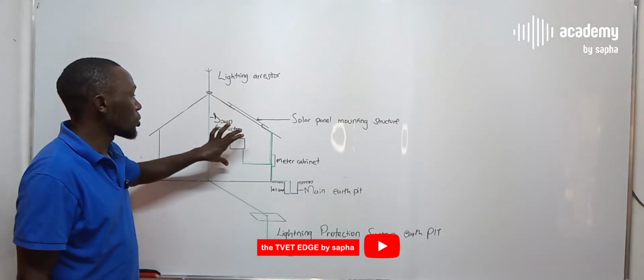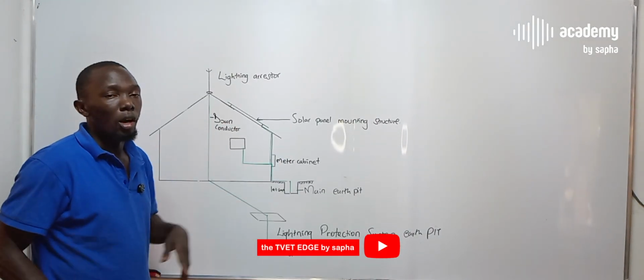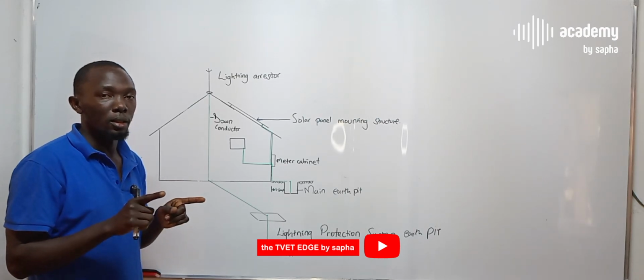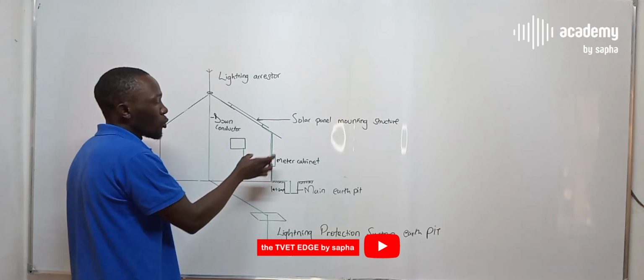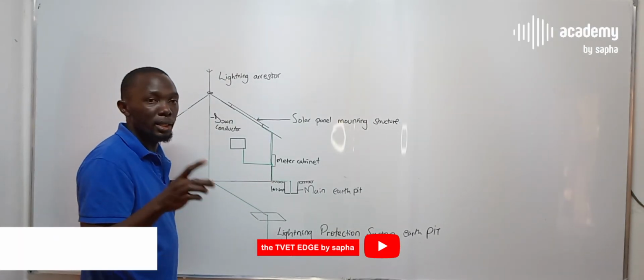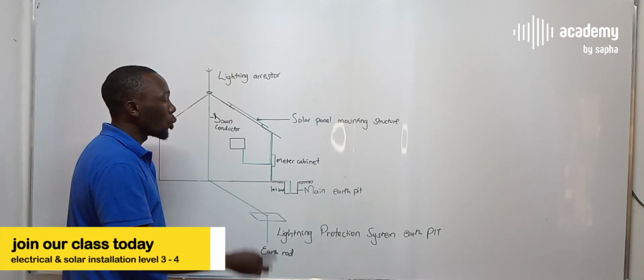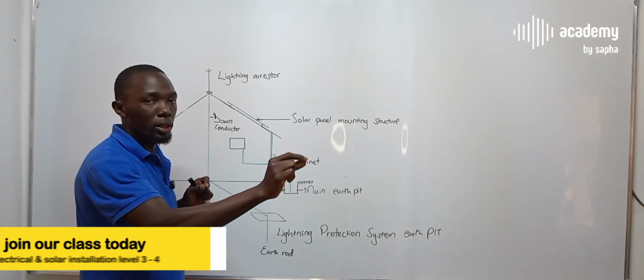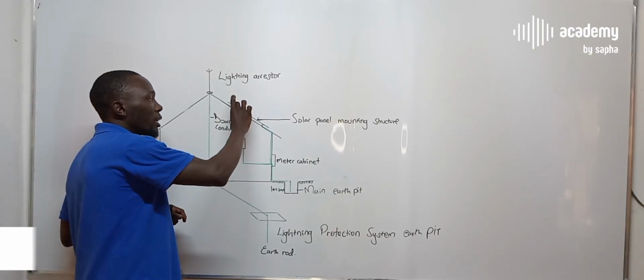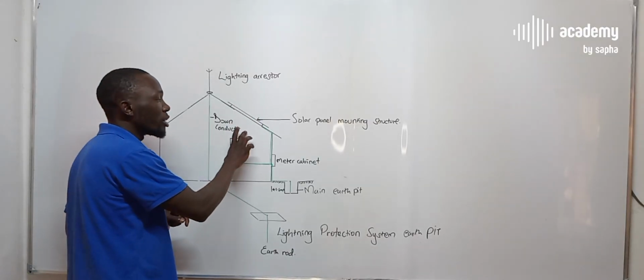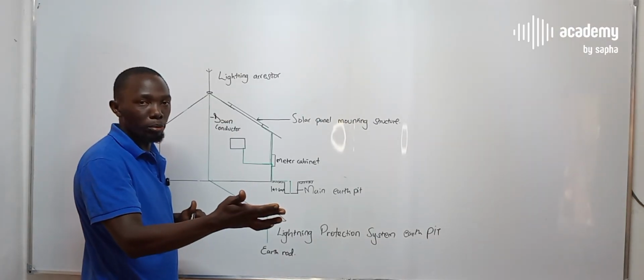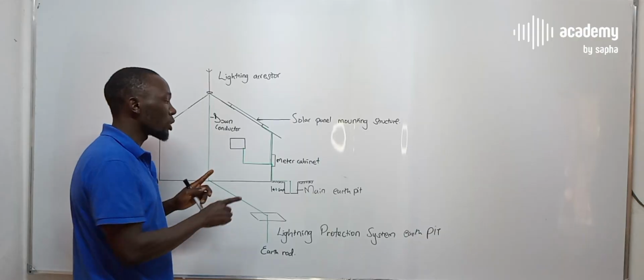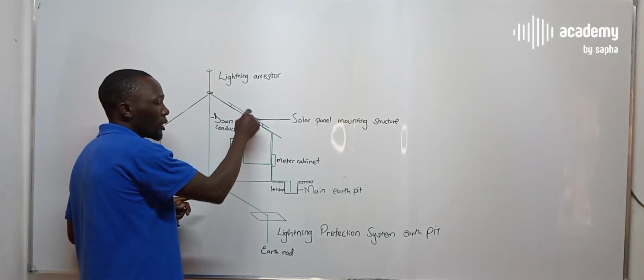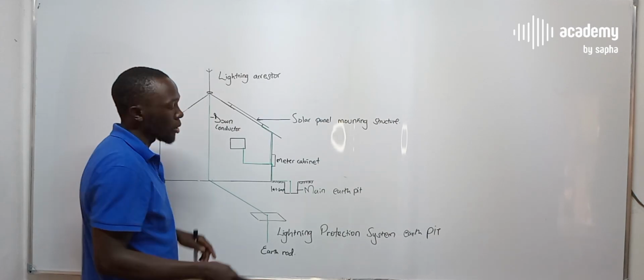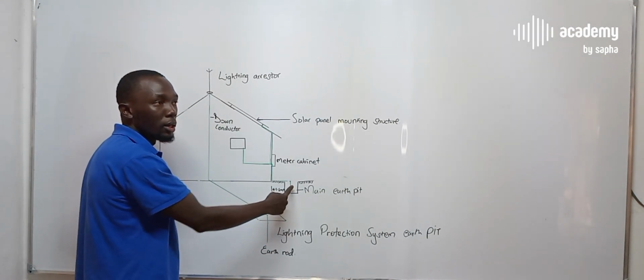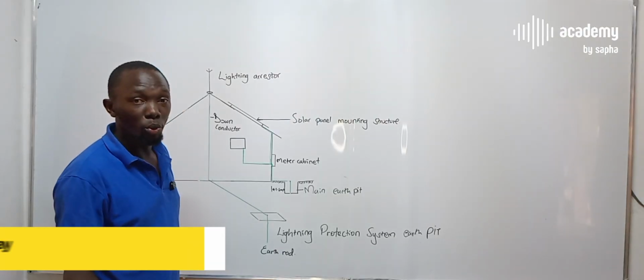So essentially this prevents the solar system and the mains electricity from having two different potentials. When you bond them together, whatever potential rise happens on the CPC or the earthing system will rise and fall equivalently. So the frame of the inverter and the frames of the panels will not have a different earthing potential to the rest of the components in the house or the accessories. So it's essential that you bond the inverter and the panels to the mains earthing system, using the main earth pit. Different configurations will require you to have more than one earth pit.